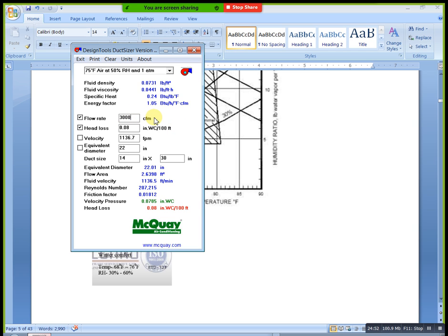Here it mainly depends upon the friction. Here the friction is completely constant. That condition we need to change this value. You can apply any two values. For example, take the constant velocity condition, where we have velocity constant. In the same way, in the equal friction method the friction is constant. In that condition, the velocity depends upon your CFM, and it changes automatically.